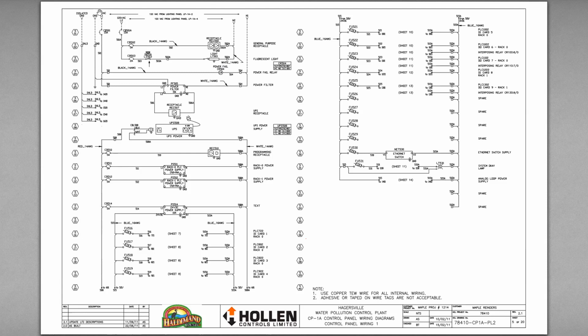When you look here at the top, you'll see that this is 120 VAC. So that's volts AC from a lighting panel. A lighting panel is just going to be the source. So that's going to be like a breaker panel that you would have in your house typically. And then the lighting circuit for this one, the lighting panel is A12. The most important information to pull from that is that you have 120 volts coming into this panel, and this particular one looks like it has an L1 and an L2, which means that there are two line feeds coming in, two 120 volts coming in.